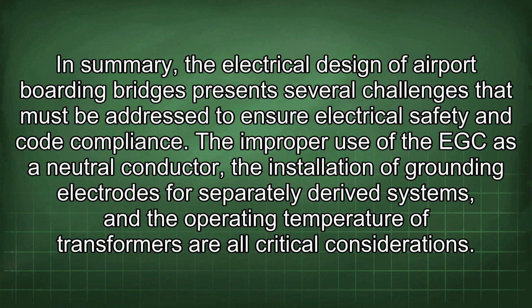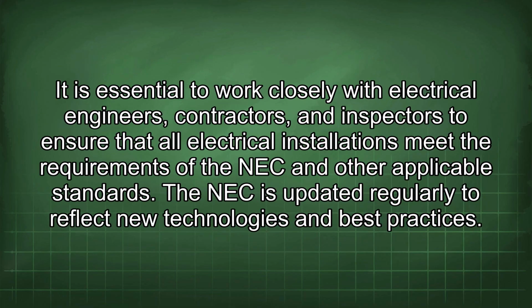In summary, the electrical design of airport boarding bridges presents several challenges that must be addressed to ensure electrical safety and code compliance. The improper use of the EGC as a neutral conductor, the installation of grounding electrodes for separately derived systems, and the operating temperature of transformers are all critical considerations. It is essential to work closely with electrical engineers, contractors, and inspectors to ensure that all electrical installations meet the requirements of the NEC and other applicable standards.